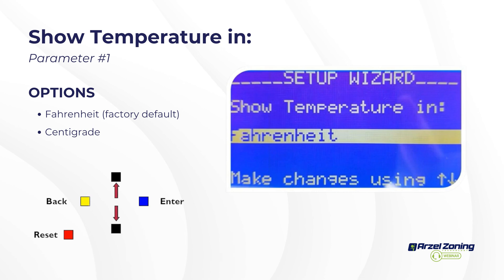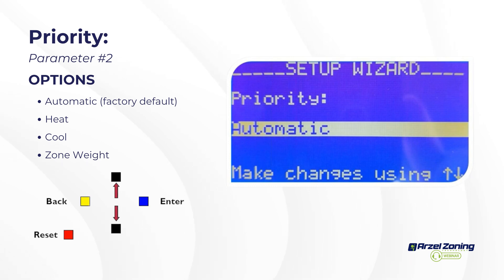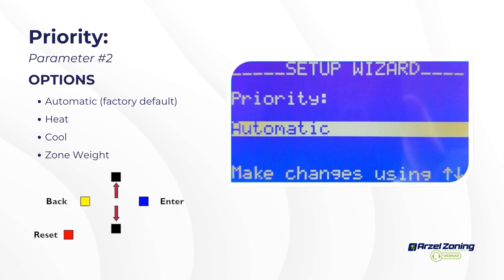You can select your zone priority. Automatic is the factory default and covers the vast majority of applications. However, some situations require a priority set to heating or cooling — for example, if someone in the house is on oxygen or has COPD and can't handle heat, you would set the priority to cooling so that zone is served first for their comfort.